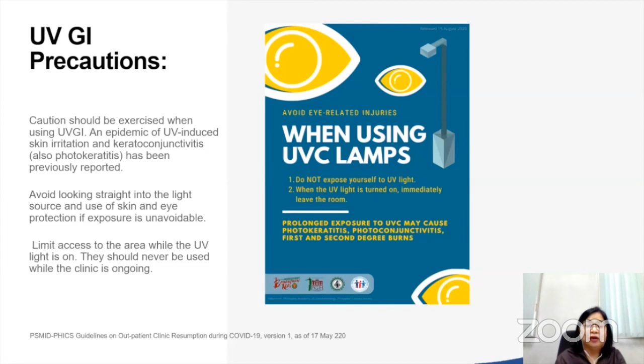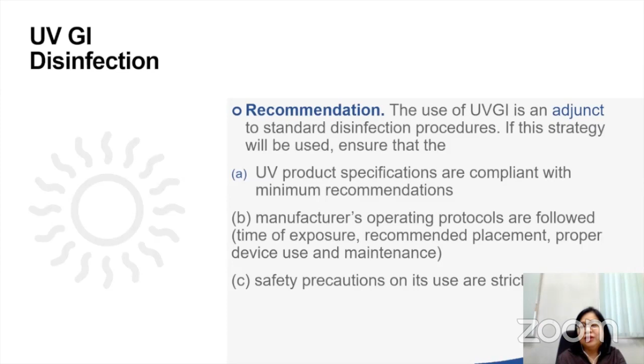The standard recommendation is that it's an adjunct to standard disinfection procedure. So what does adjunct mean? First, you clean, mop everything, wipe everything, and then you want to be very sure, so you expose to UV light. Make sure that the UV product specifications are compliant with the minimum recommendations, and that the protocol for using the equipment follows the manufacturer's protocols, because we have to be very safe. You have to really make sure that you are safe.